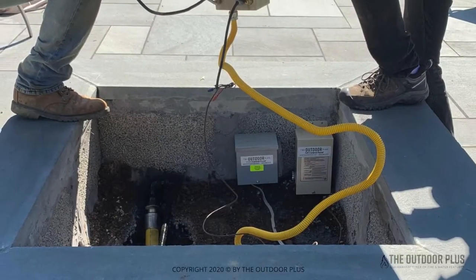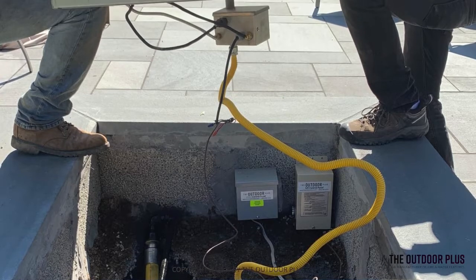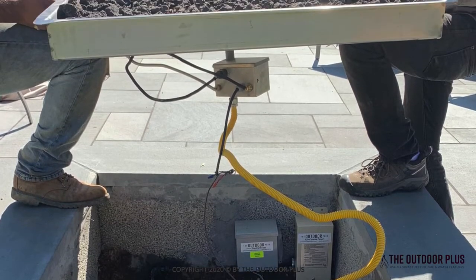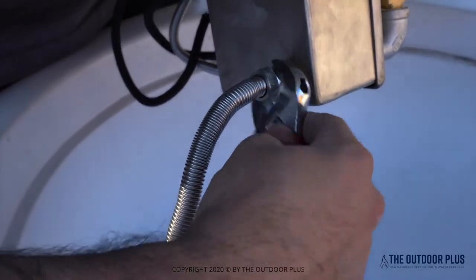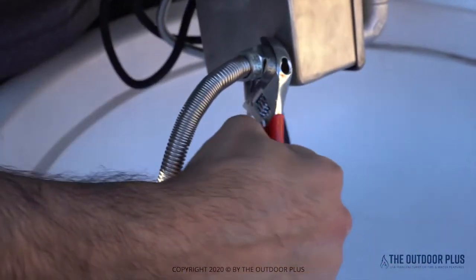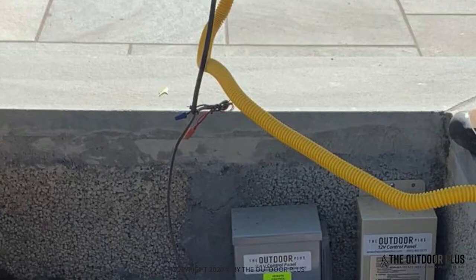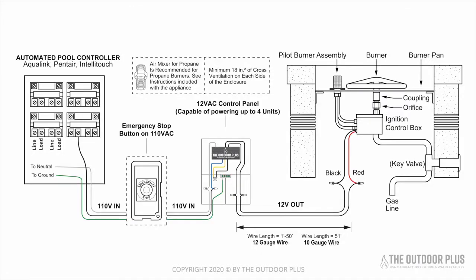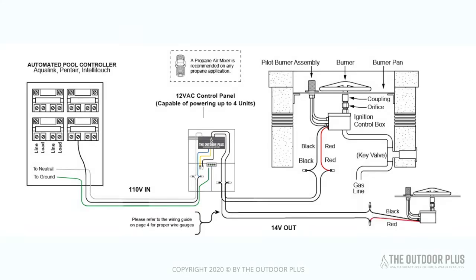Do not use a yellow gas flex hose. This will create a loud whistling sound. Instead, please use a stainless steel whistle-free flex hose when connecting your gas lines. Do not use anything less than 12 gauge wire. This particular installation used 14 gauge wire and did not get enough power to the electronic system. Our electronic fire features are compatible with home automation and pool controllers.